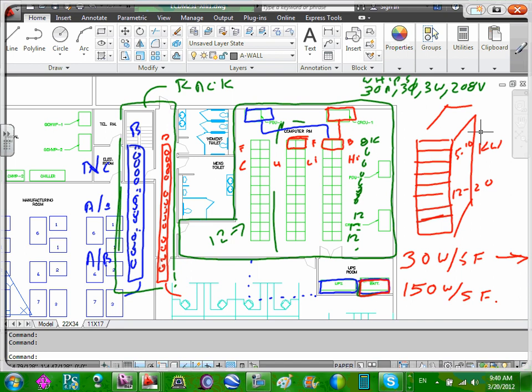So all of this is in there so that each and every server in that rack would then plug into the appropriate plug strip. You can buy colored cords for your server. So sophisticated owners are buying blue and red cords, if that's our color choice, taking the black ones, throwing them away. This has a blue nameplate on it, and this has a red nameplate, and this is blue seal tight, and this is red seal tight. So it's a real visual certainty that everything's plugged in right.